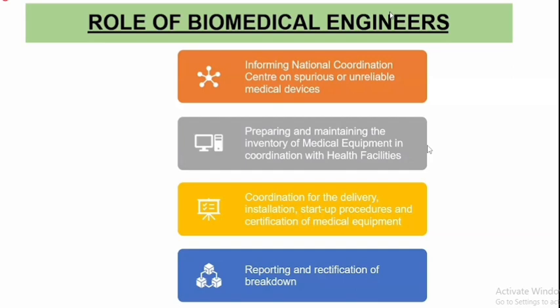Other roles and activities include preparing and maintaining the inventory of medical equipment in coordination with their health facilities, coordination for the delivery, installation, startup procedures and certification of medical equipment, and reporting and rectification of the breakdown of any medical device also.